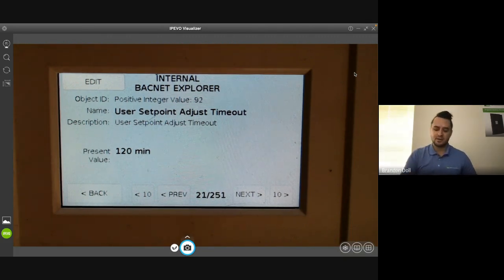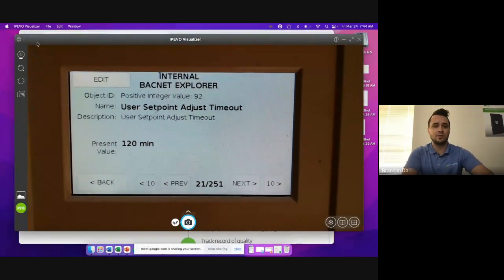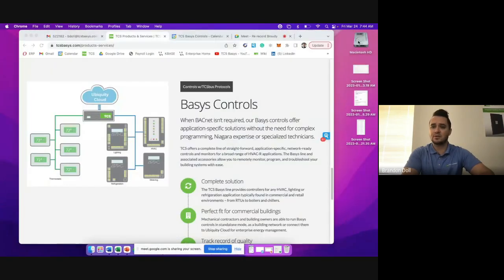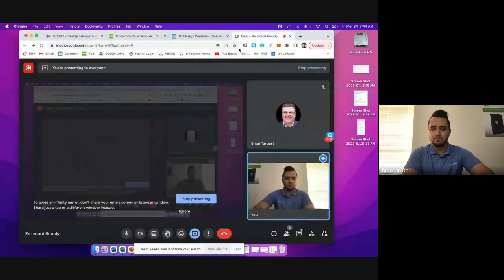Now in this internal BACnet Explorer, that's how you set up your minimum damper position, maximum damper position, CO2 demand ventilation, pre-occupancy purge. I apologize, I don't memorize all 251 open and commandable BACnet points, but contact your Brody Precision rep, and they can definitely hook you up with a list of those BACnet points, or help you navigate through the system for you.